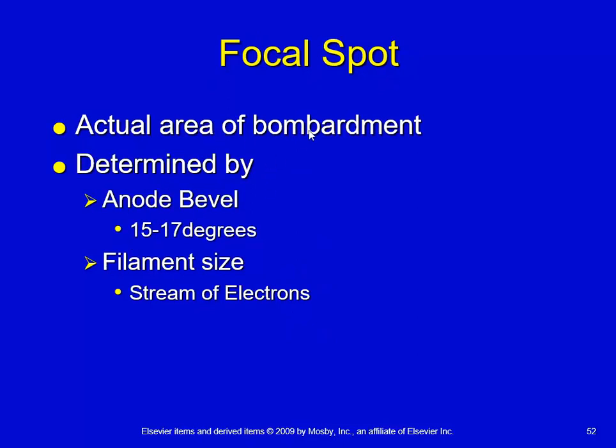This is the actual focal spot. We also have what we call the projected focal spot, or the effective focal spot — what the patient would see if lying on the table and looking up at the anode. Because the anode is at such a steep angulation, it's kind of like holding a pin perpendicular to your line of sight and then tilting it until it's almost parallel — the pin looks very much smaller.